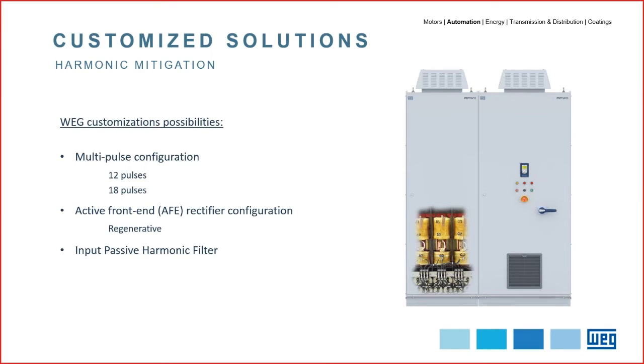The last possibility and consideration I will present to you is the inclusion of a passive harmonic filter in the VSD input. Passive harmonic filters are reliable when they are well sized to the application. They will ensure the correct harmonic mitigation and also keep the system efficiency at higher levels. The passive harmonic filter is also responsible for correcting the complete frequency harmonic spectrum, avoiding any unexpected situation during operation. This is actually one of the most sought after configurations for our customers.